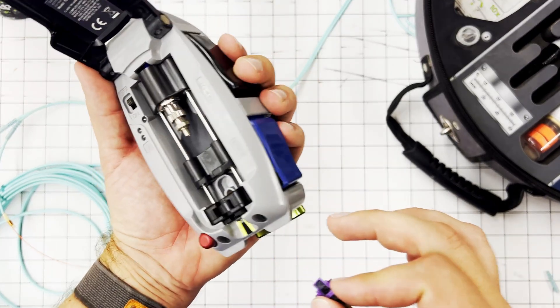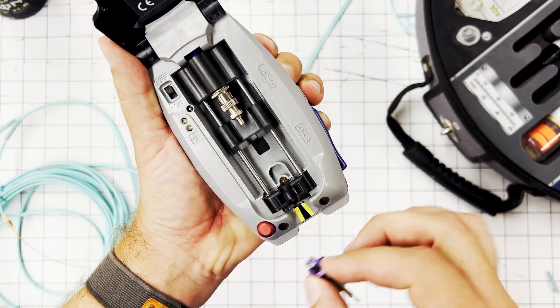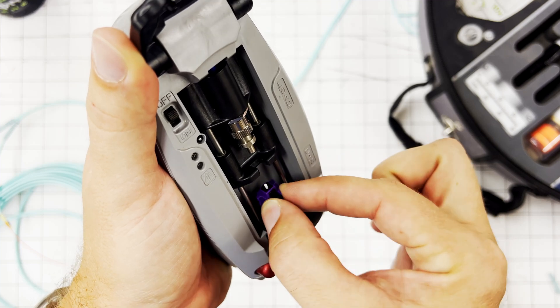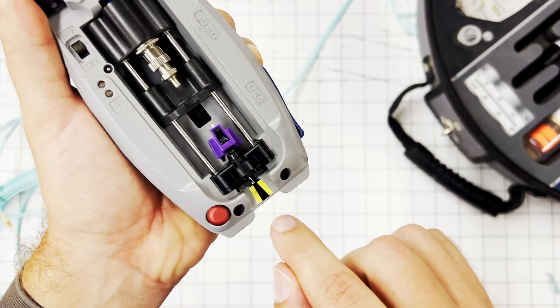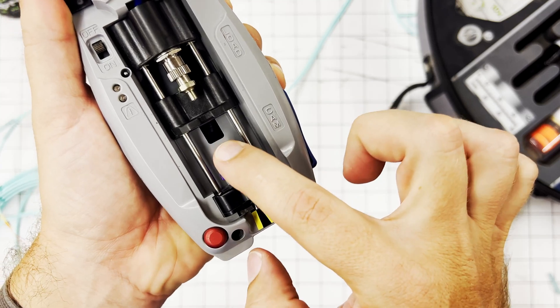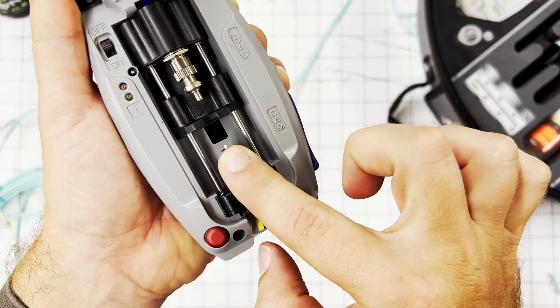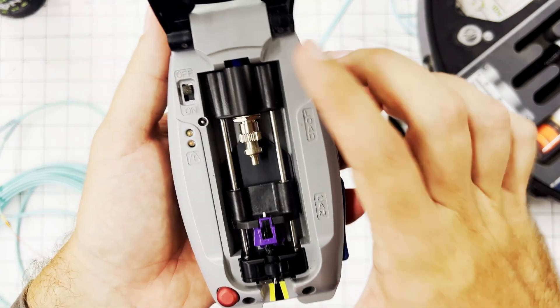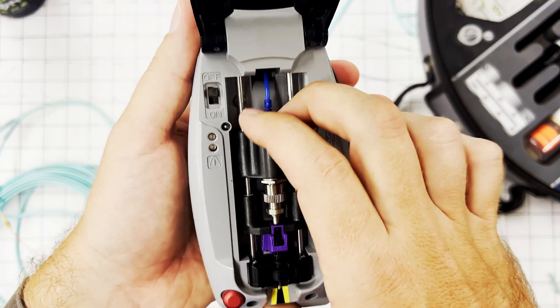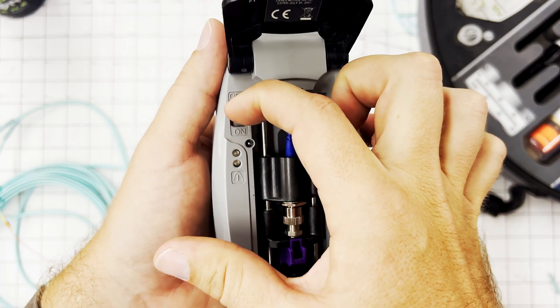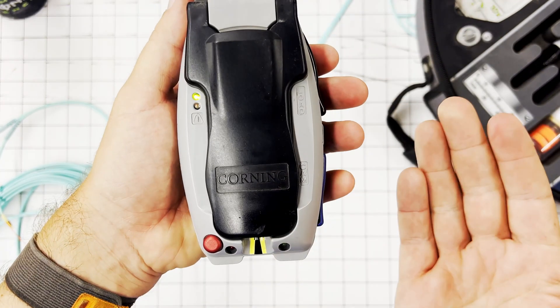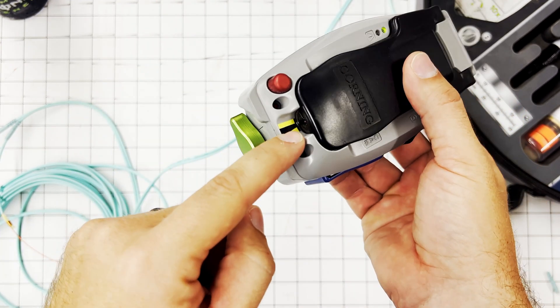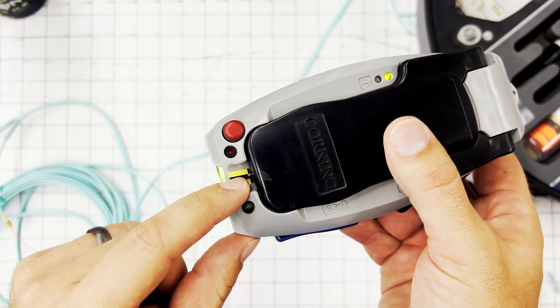Press your red. Put it off the bat. Squeeze and hold the black. That raises this up and down. Take the back end of this. And you want to put it down into the hole of your cam tool. Until it's seated. This is coming out the bottom. This is seated snugly. And then slowly let go of your load lever. And it grabs it. Then pull this down until it clicks. Make sure your tool is on. Close the door. We're good. Now we're just going to set this to the side. Make sure no dirt gets in here. Or else this termination is bad. And you need to get another one.